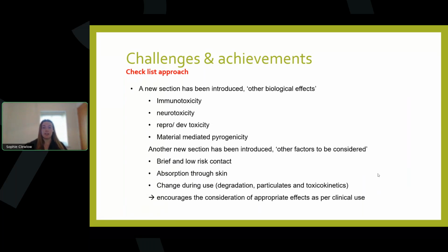There's also another new section, and that's other factors to consider. This includes medical devices with very brief contact, absorption through the skin or mucosal membrane, and materials that change during use, including considerations of degradation, particulates, and toxicokinetics. With regards to medical devices with very brief contact, this section provides guidance on devices that typically have contact for less than 1 minute, such as lancets or hypodermic needles. It then goes on to discuss the ability to prepare a written justification regarding negligible potential for biological harm.